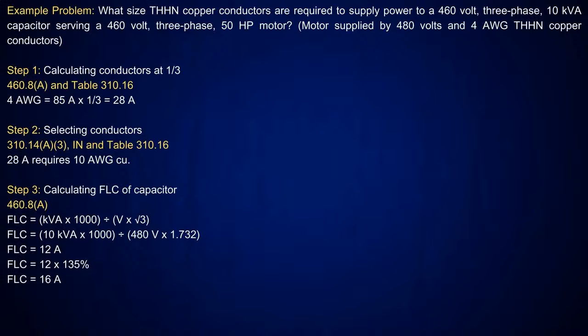Now, this is where I've got a capacitor. I've got a 460 volt 3-phase 10 kVA capacitor, and it's going to serve a 460 volt 3-phase 50 horsepower motor. We're already giving you the information here. The motor is supplied by 480 volts, and it has number 4 THHN copper conductors. So if I look at a number 4 conductor and go over to Table 310.16 and come down to the 75 degrees C column, it's going to tell you it's good for 85 amps. So I'm going to take that at a third. And you'll say, where did I get the third? Well, you go look at 460.8(A). That's going to tell you to take it at a third, and that gives me 28 amps.